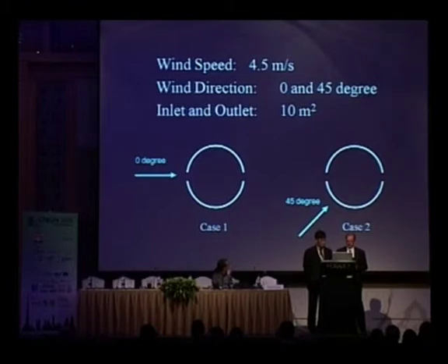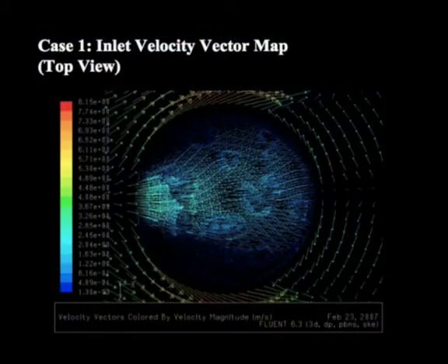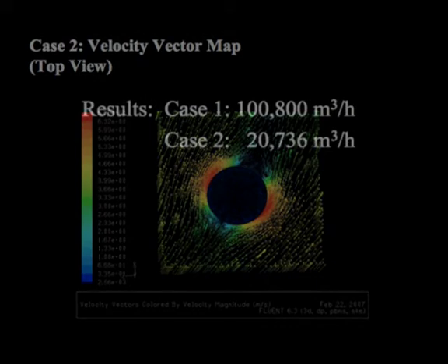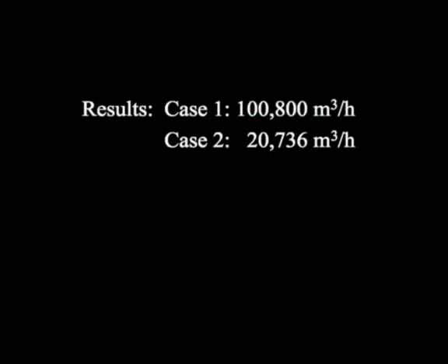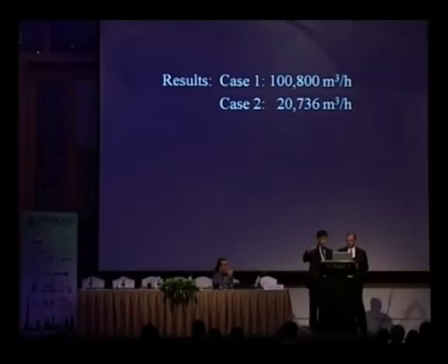Some case studies looked at a wind speed of 4.5 meters per second, with outlet and inlet sizes relatively small compared to the volume of the atrium. The analyses showed that case 1, facing one direction, gave about 5 times the ventilation of case 2. Simply turning the opening 45 degrees to face the wind gave 5 times as much—just subtle differences like that. So you either work with the prevailing wind, or build in a system that actively or dynamically changes the location of that opening.